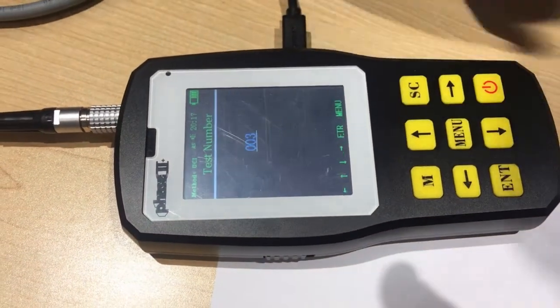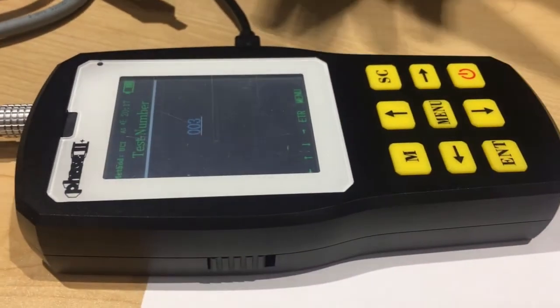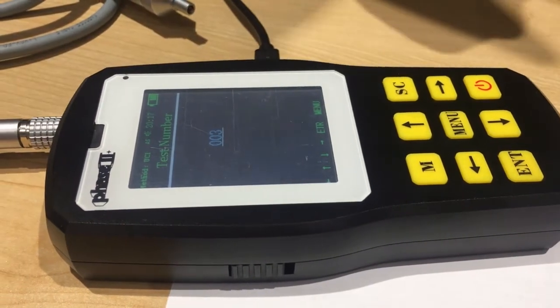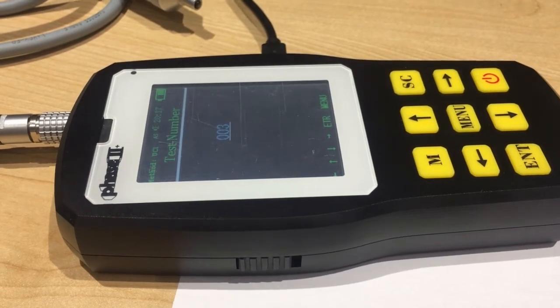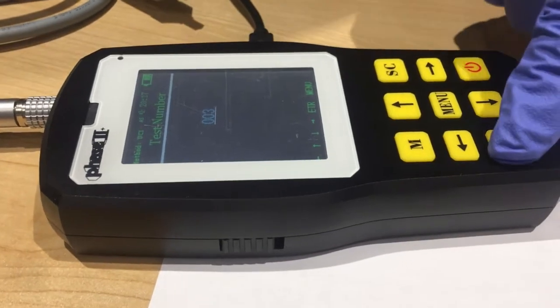We got some other options here. The main things we are going to focus on is the test number. Test number means how many times you want to test to get an average for the hardness you want. So it basically depends on yourself. Here we set it as three, that means we test three times and get an average to decide the hardness number. If you are sure for it, press enter again.